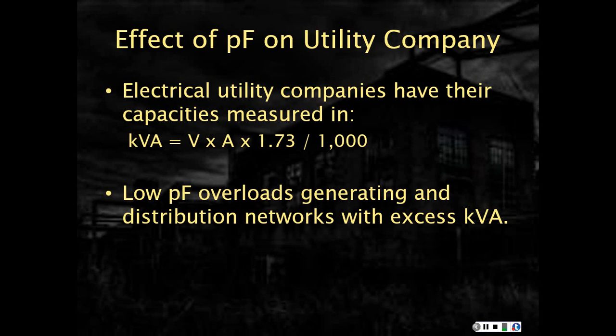Now, on the other hand, let's take a look at the effect of power factor on the utility company. The electrical utility company measures their capacity again in kVA, or apparent power. So kVA equals volts times amps times 1.73 divided by 1,000 to get it into kilo. Low power factor overloads the generation and distribution network with excessive kVA.